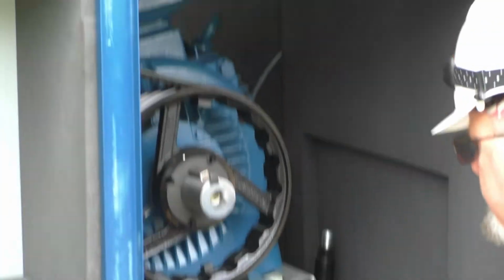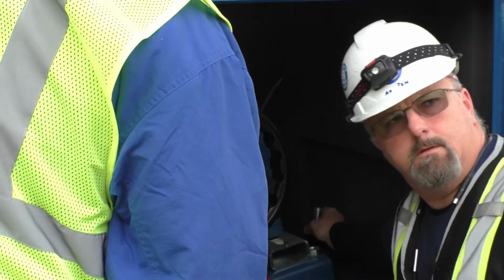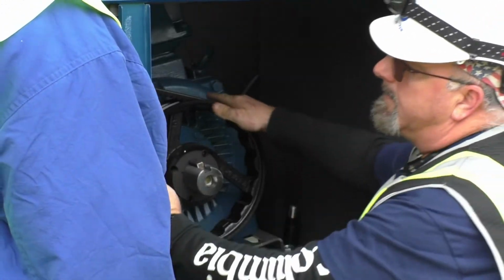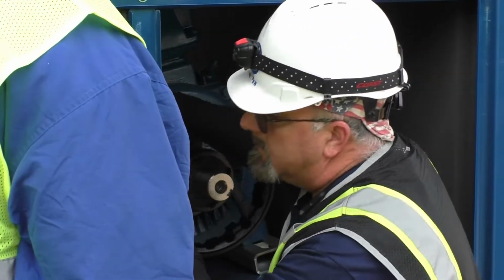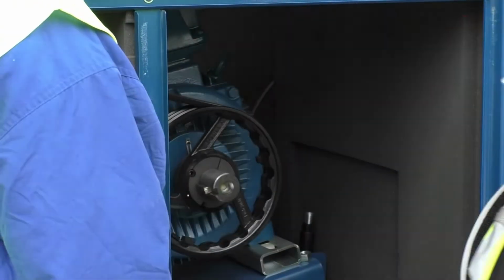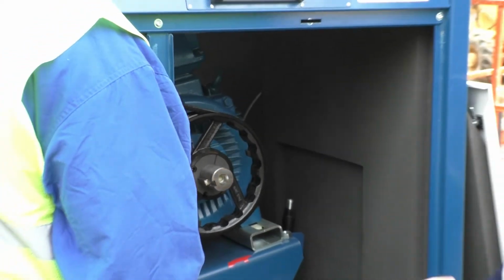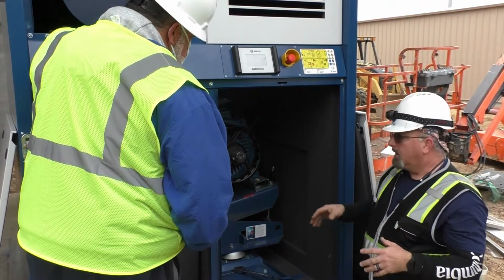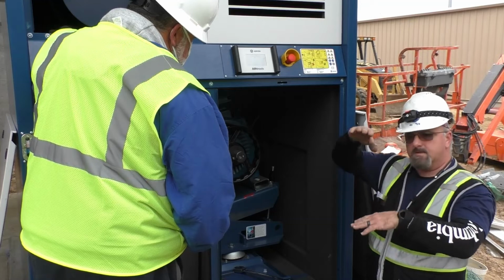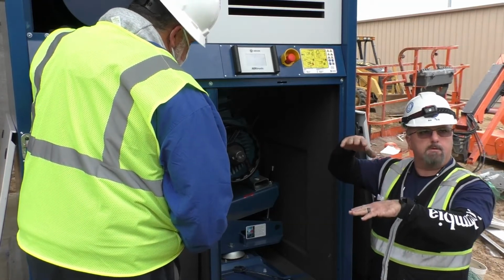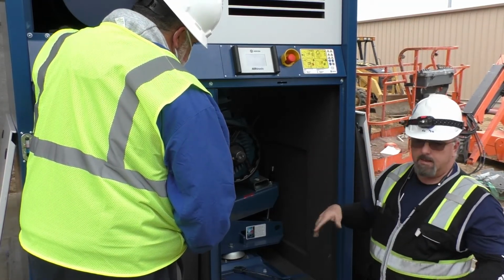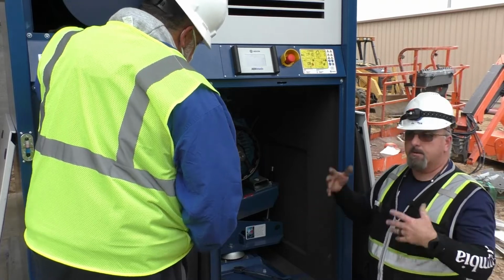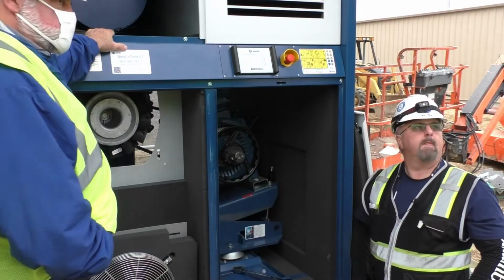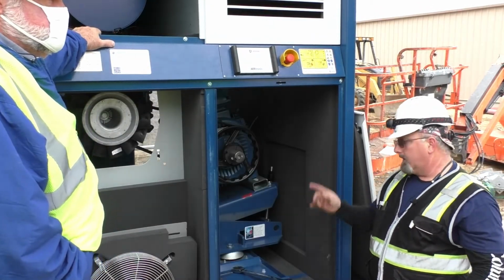All right, once you have it loose enough where you can turn it by hand, take your motor, spin it, because sometimes with the belt memory of the belts being shipped, they may have one that's tighter on the top, one that's tighter on the bottom. When you rotate that lets it normalize to where they're all the same tension. So the tension of those belts is determined by the weight of the motor? By the weight of the motor.